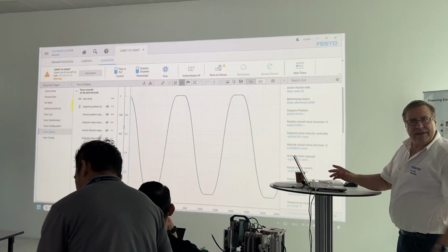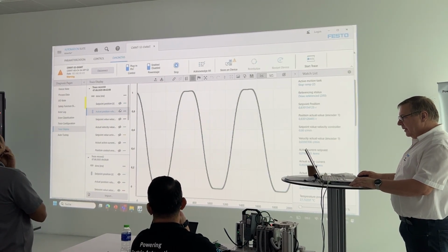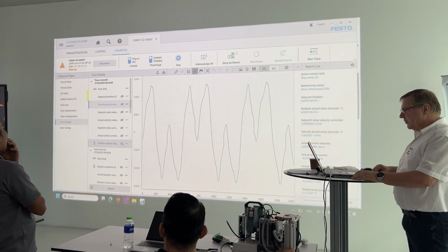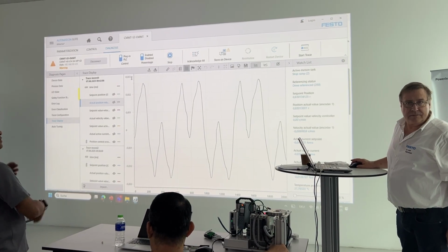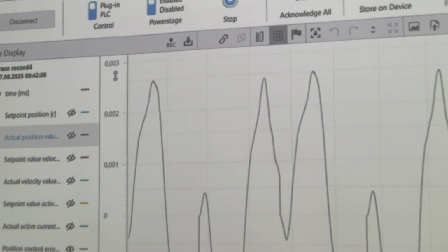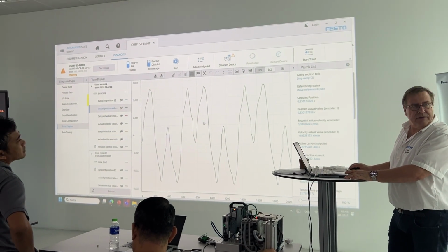And of course, if you are only observing the positioning failure, this is perfect. You cannot see anything. By the way, we never see anything in this part, because it's mostly not working when it's so bad. In the current you see something, and maybe in the position error, where we are talking about 0.003 turns. We calculate how much that is, and it's very small.